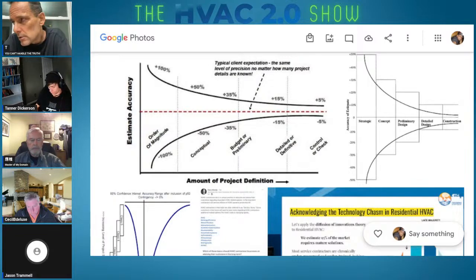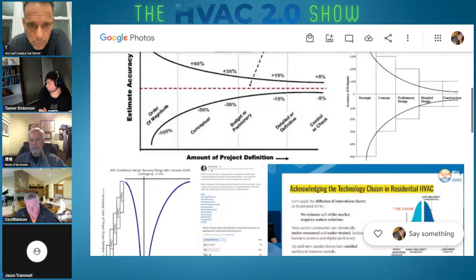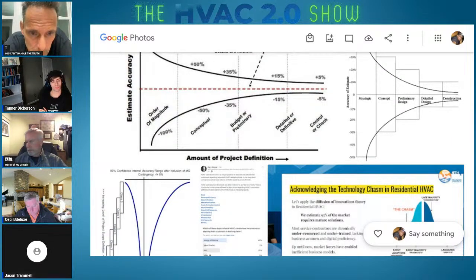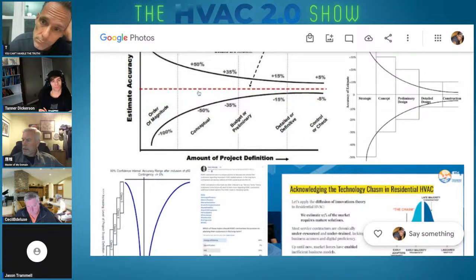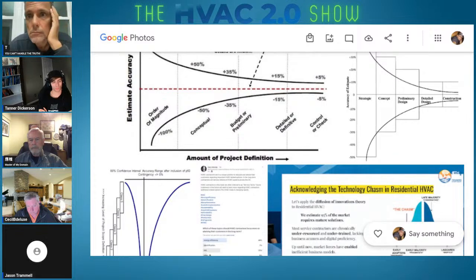Yeah. And then there is the only real issue with oversized ductwork, and it's really not oversized ductwork. It's oversized outlets, like diffusers. If you have, quote unquote, too big of outlets and you put in multi-stage or variable capacity equipment, then when it's on a lower stage, it's going to put more air out of the vents closer to the unit than out of the ones furthest away. So there can be some issues. Now you can always block off half of the registers closest once you replace the equipment and balance it out. But there is some credence to that. But that's really the only thing with oversized ductwork, and that's really a distribution problem, not the ductwork itself. It's a problem with the terminal velocity. You're not getting mixing and spreading out through the room.